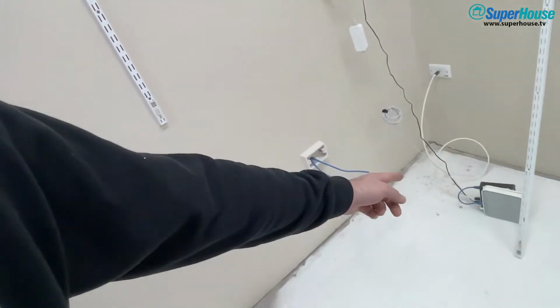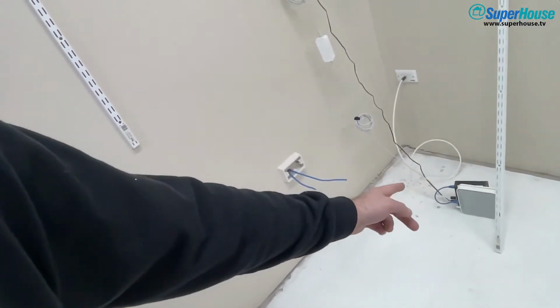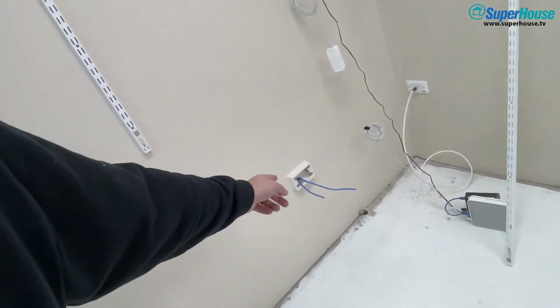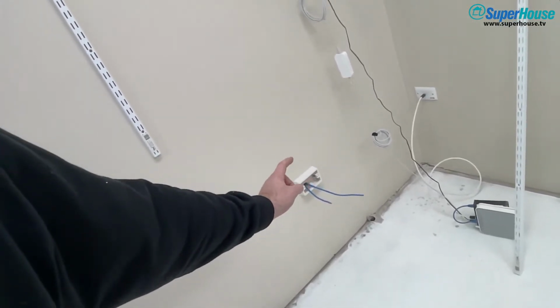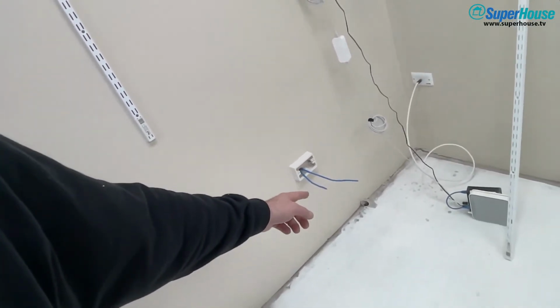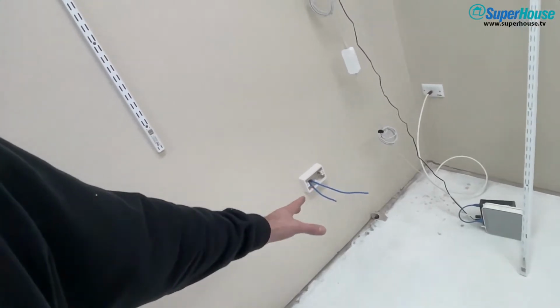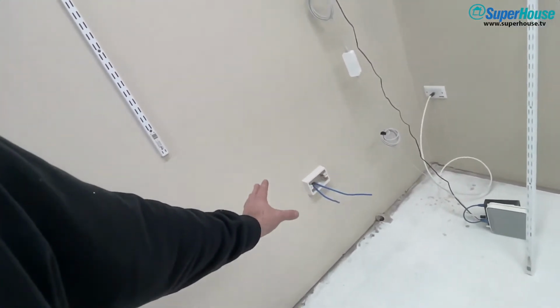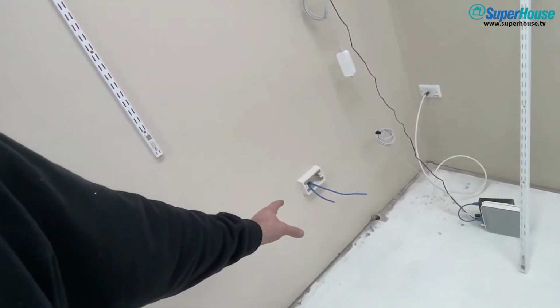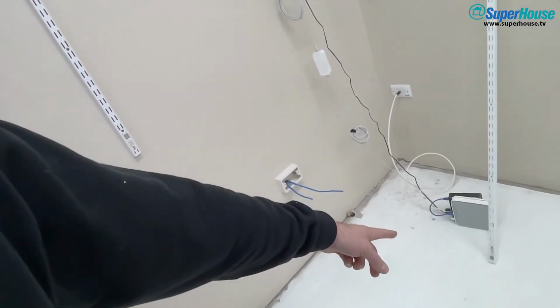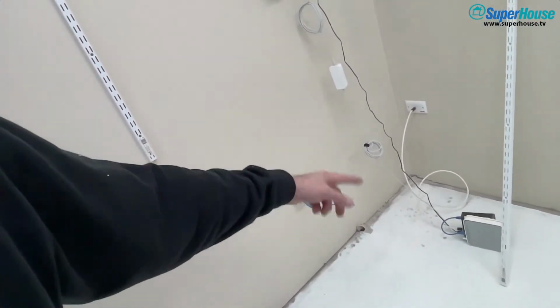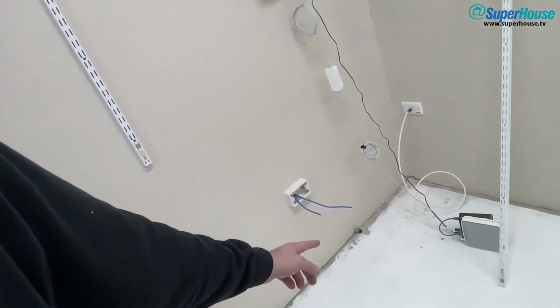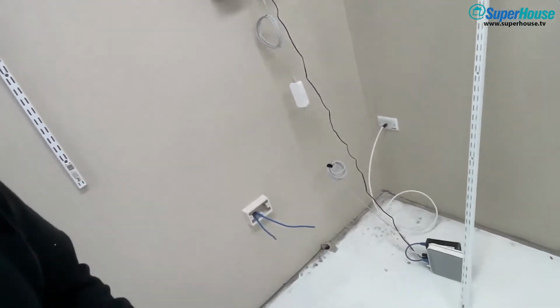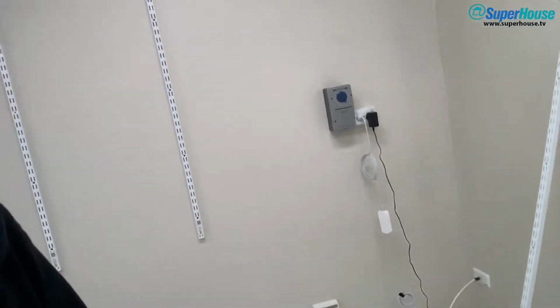The reason I want to run the network termination device on power over Ethernet is that I want to power it from the UPS that will be in the rack. All of the network infrastructure will be on the UPS, including the network termination device. That's why I don't want it just sitting out here plugged into a GPO - it'll get its power via the network cable.